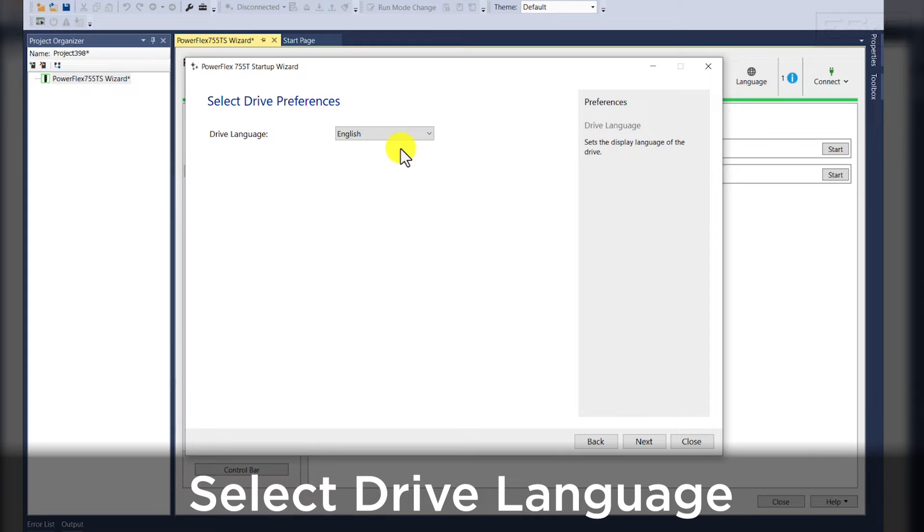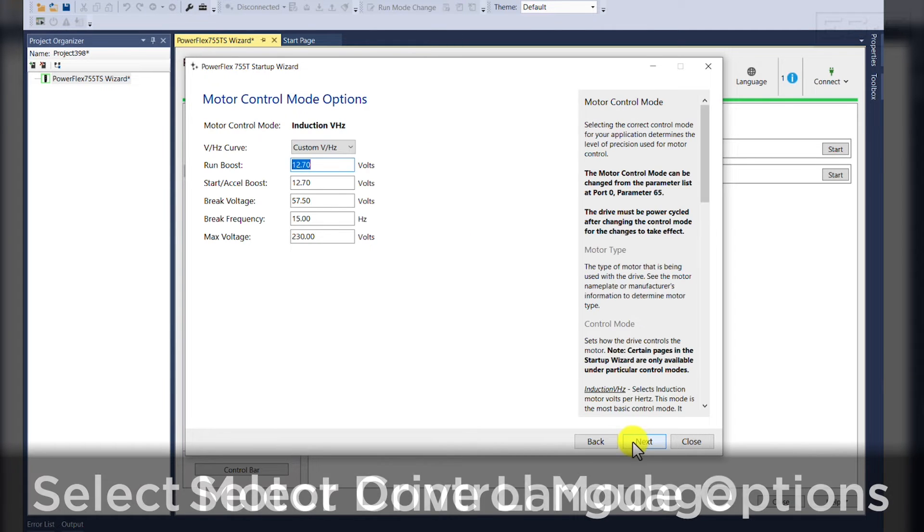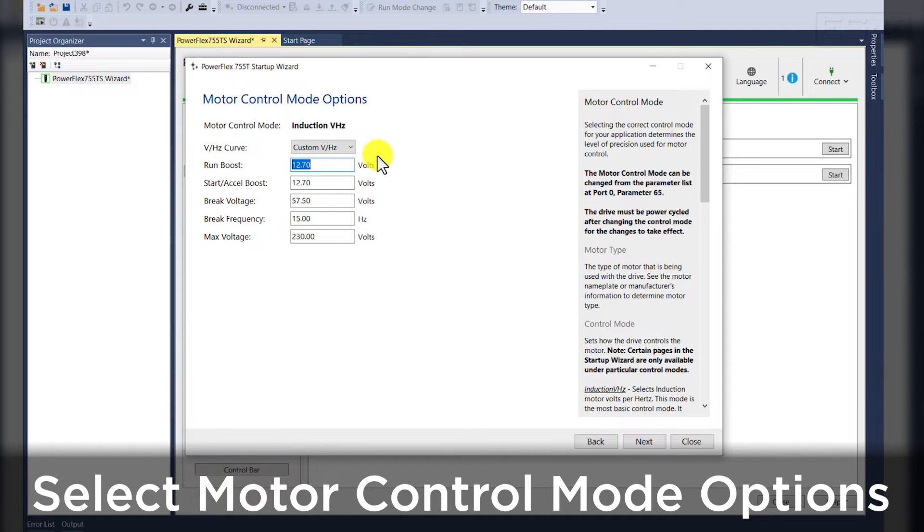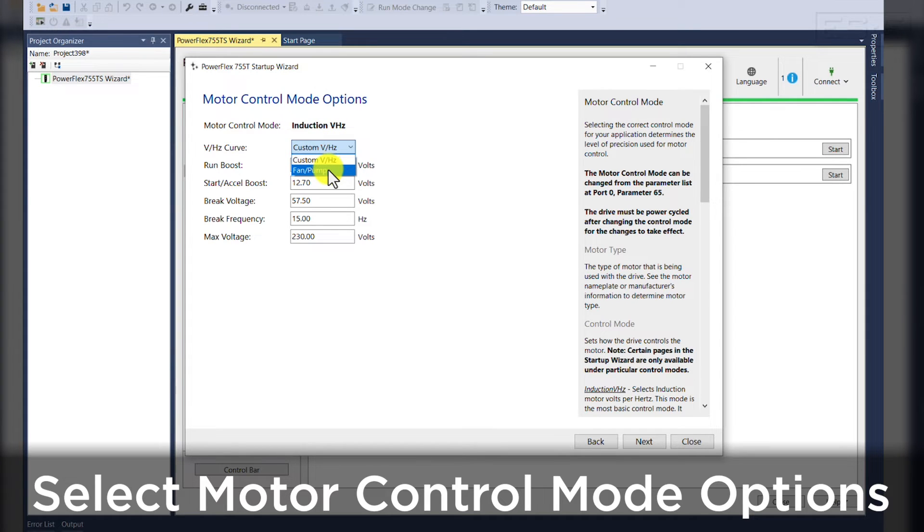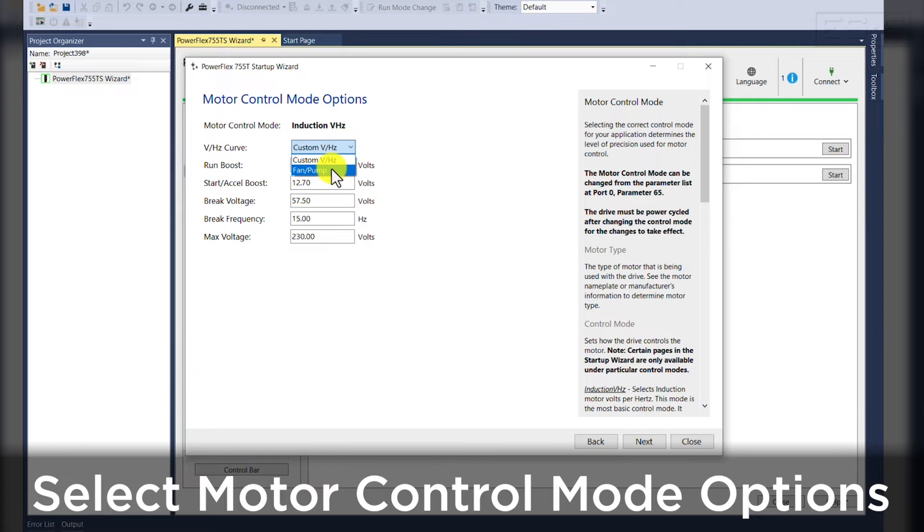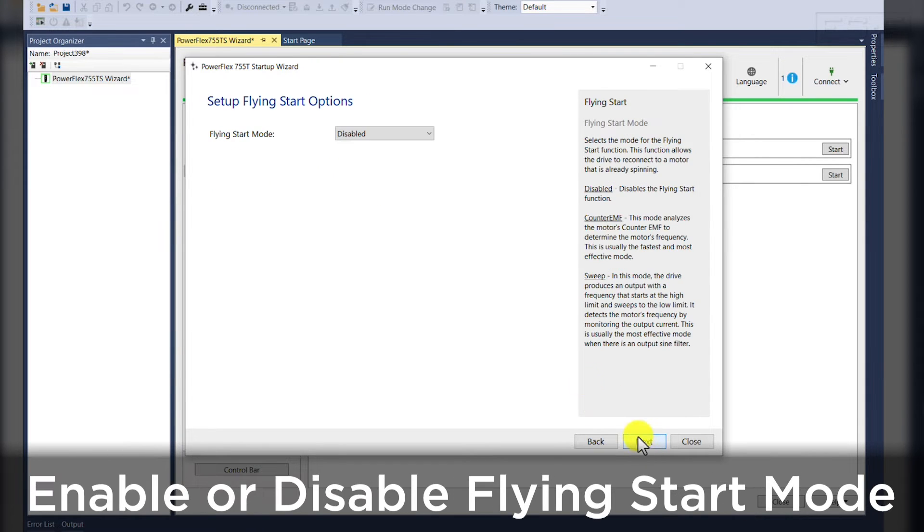So we will select the drive language, which is going to be English. Our motor control method is going to be induction volts per hertz. We'll set this to fan and pump so we don't need a custom volts per hertz curve.